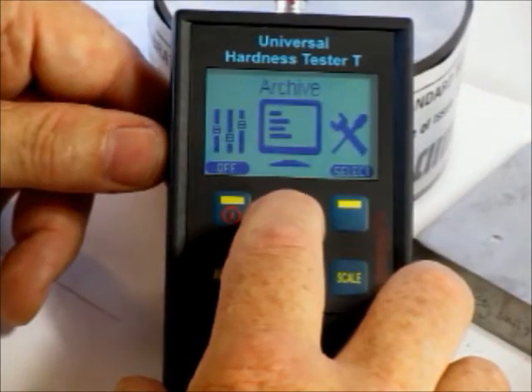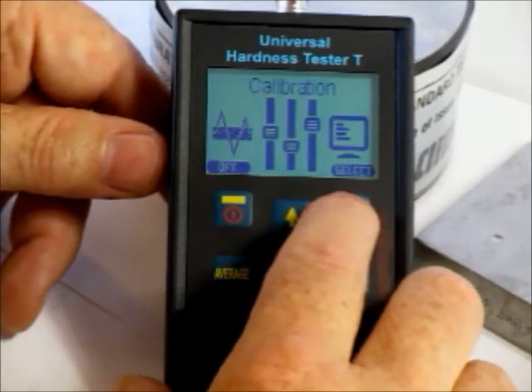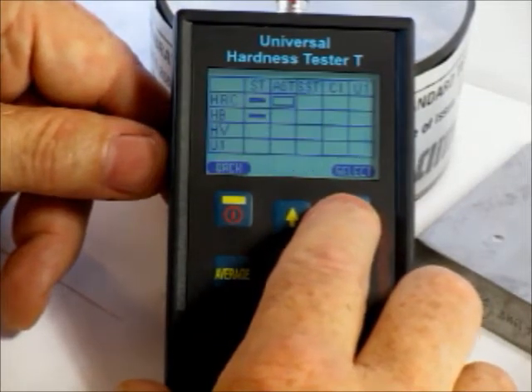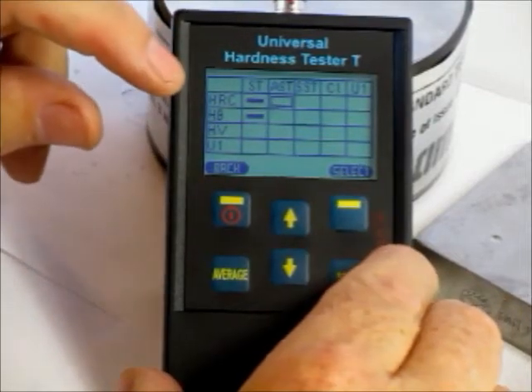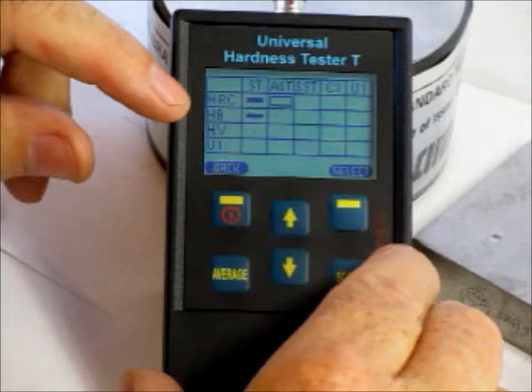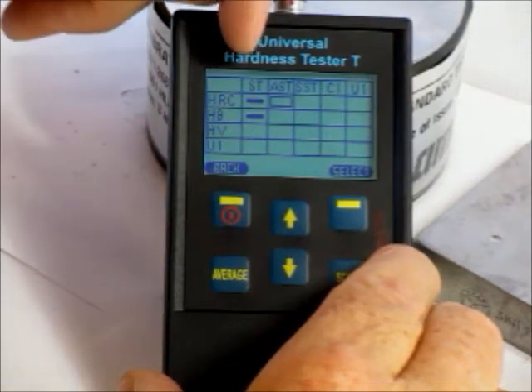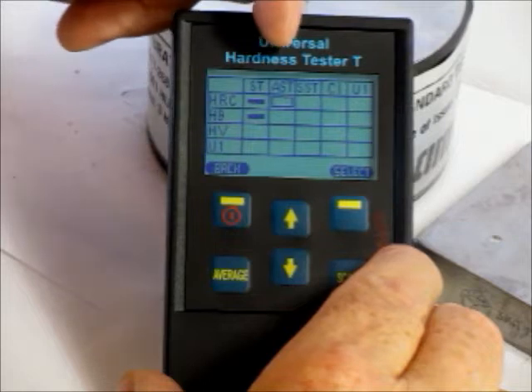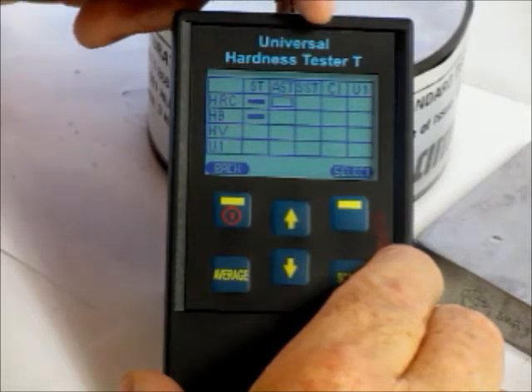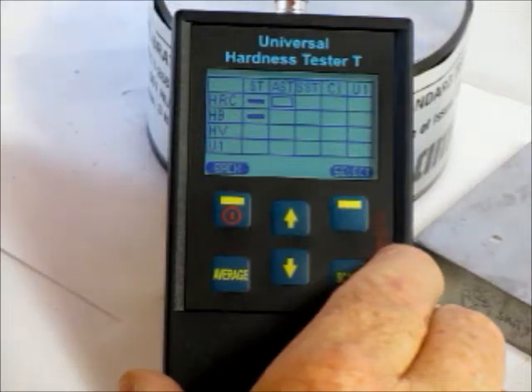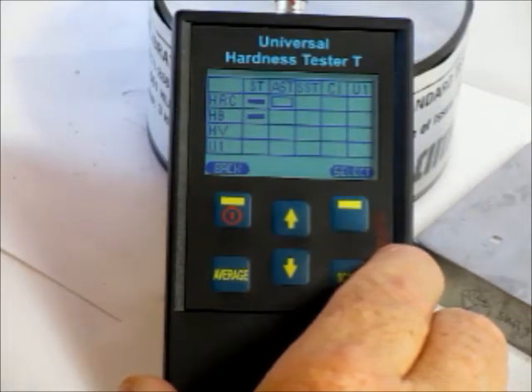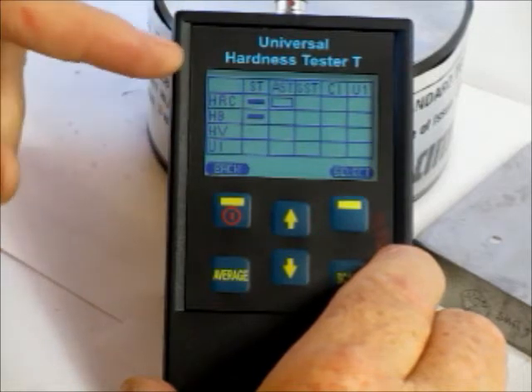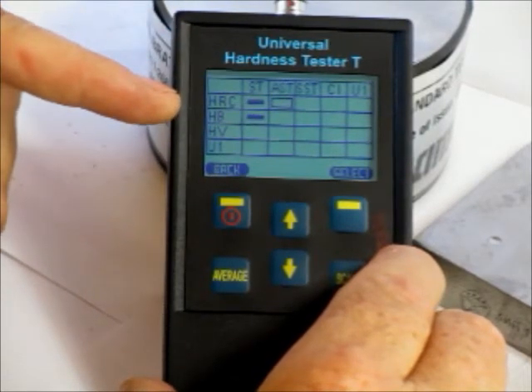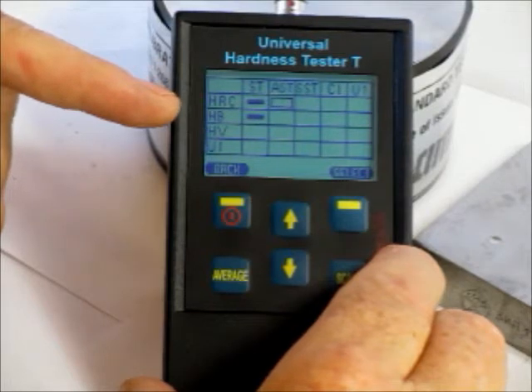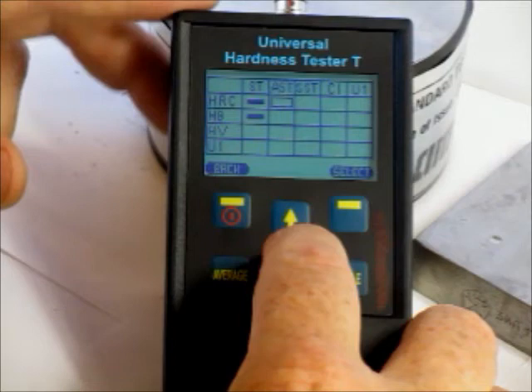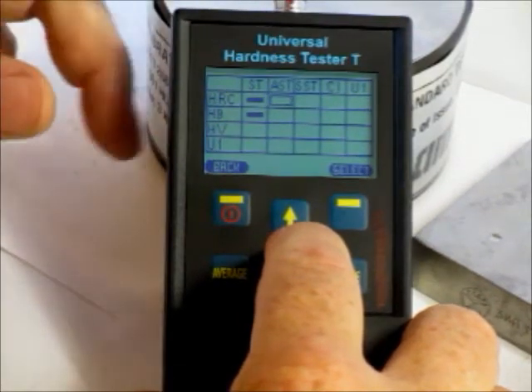So if I scroll back to calibration, we're on the calibration display, hit the select button, and you can see here we have the scale, so hardness and Rockwell C, Brinell, Vickers, and we have even a user defined. We can store this as just steel, or AST as alloy steel, stainless steel, and then 2 user defined ones. So you could do, say, titanium or some exotic material if you wish to. We do pre-calibrate the units for Rockwell C and Brinell for just low carbon steel or mild steels. What I'm going to be doing here is calibrating the unit for high carbon steel using my calibration test blocks.